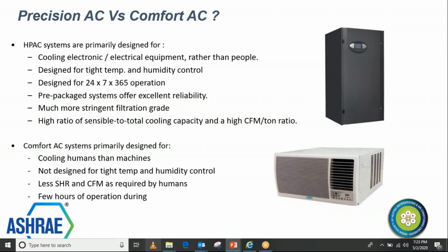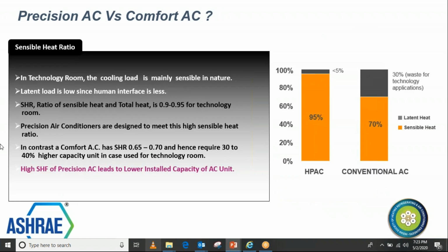So this is the basic concept difference, the design difference between these two products, these two applications, these two concepts. Moving forward, we can compare them in more detail to give you a better picture of how these are compared at every component level. Sensible heat ratio: you can see on the right side here that a comfort air conditioner is around 60 to 70% sensible and the balance latent, and the precision AC HVAC system, a high performing precision air conditioning unit, is 95 to 100% sensible cooling.